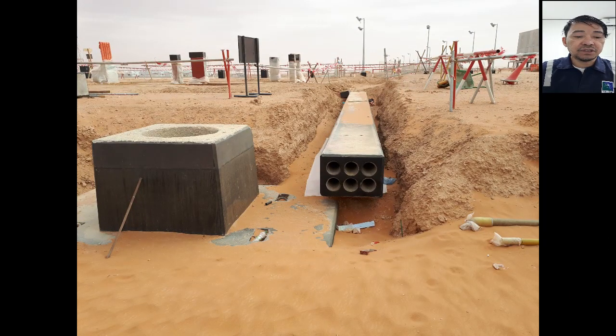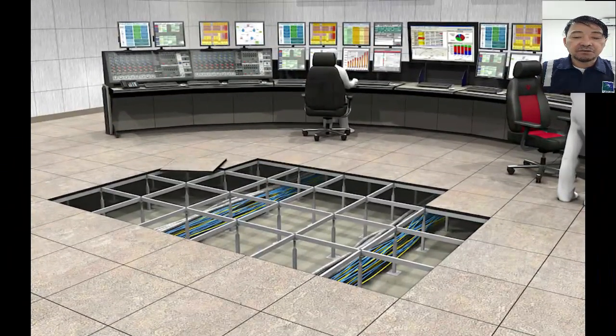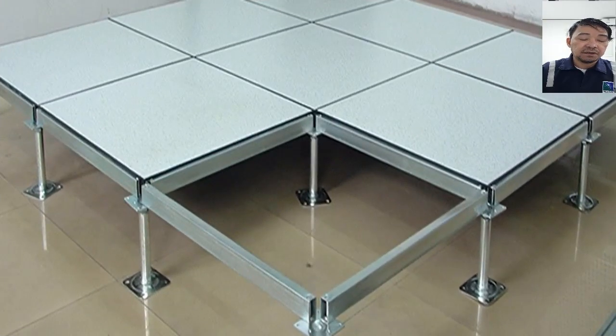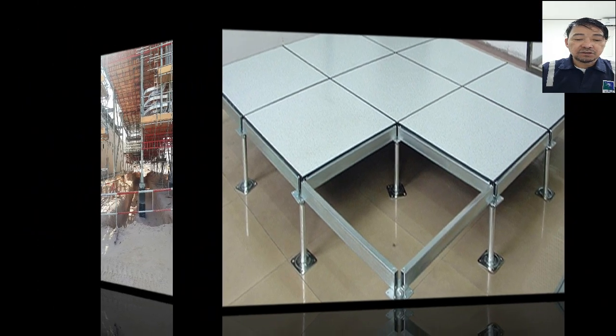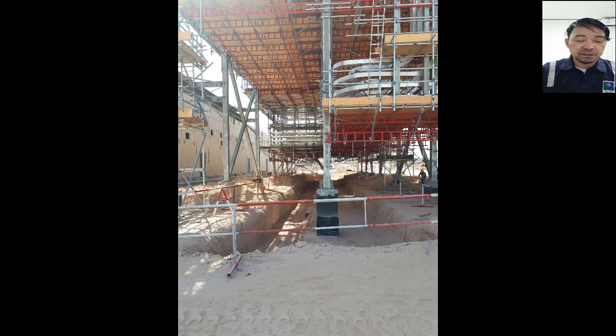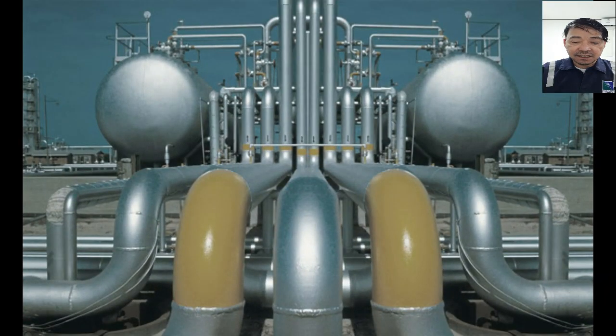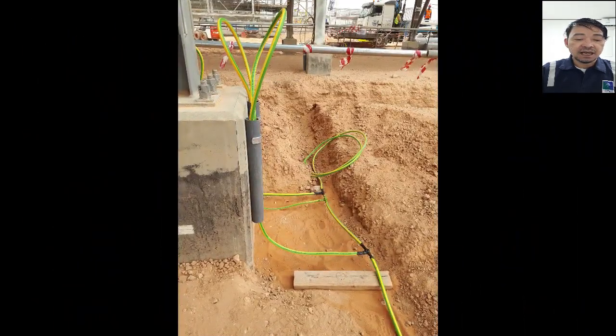Electrical manholes shall be grounded using two ground rods located close to diagonally opposite corners of the manhole. Raised computer floors shall be grounded by bonding a minimum of two pedestals at opposite corners to the nearest ground bus or grounding electrode. The following equipment shall be connected to the local ground grid, grounding electrodes or supplementary grounding electrodes. Structural steel supports, including coated structural steel for process equipment and piping, and structural steel columns for buildings at least every 25 meters.